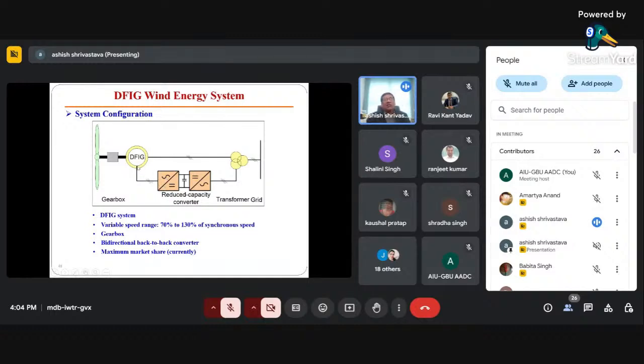It is being injected at the stator. So that's why this is the converter. Both the converters are at reduced capacity. That's why the losses are less and cost is also less. And that is the additional advantage of the doubly fed induction generator.